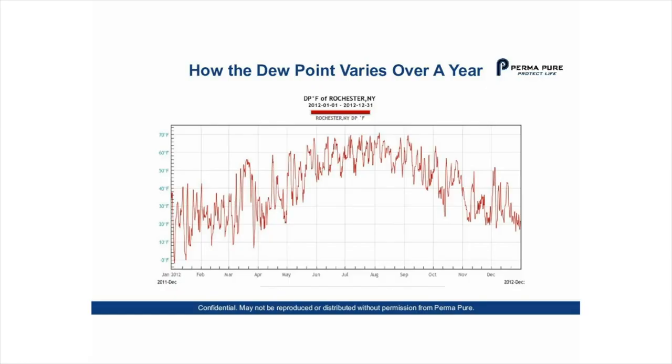You can see that not only does the dew point vary quite drastically within the month, but as the months progress, there is definitely a trend through the summer. The dew point rises through the summer and drops towards the winter. This is a sinusoidal pattern that happens over the course of the year. If you're doing any measurements of atmospheric air, or you're using atmospheric air as a purge gas in some form, even if it's under vacuum, you will get some variability in your data.